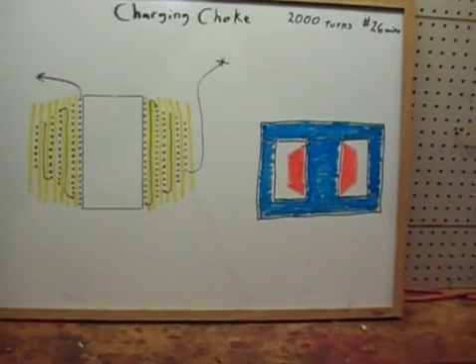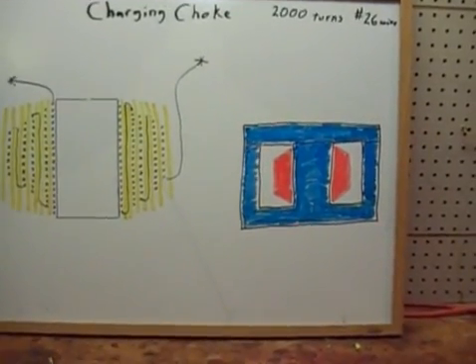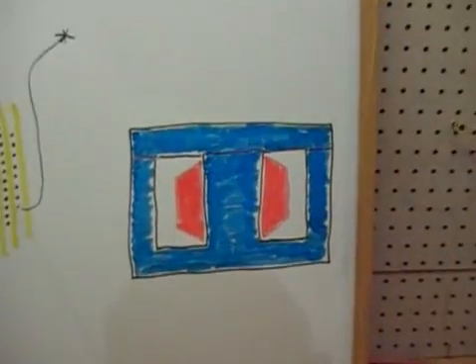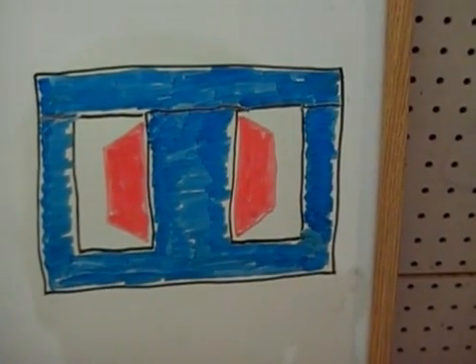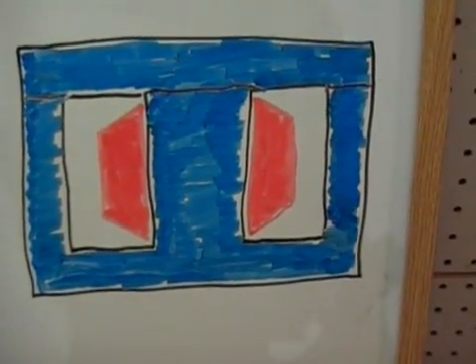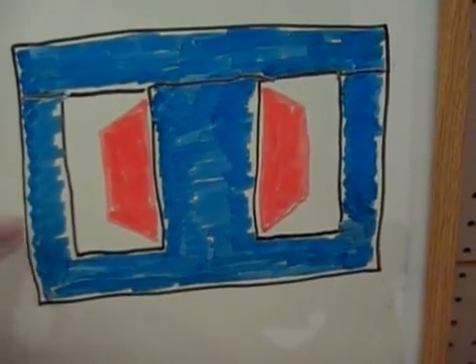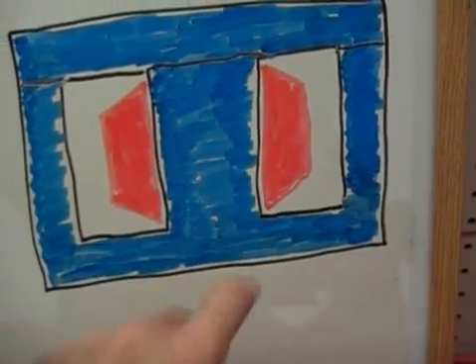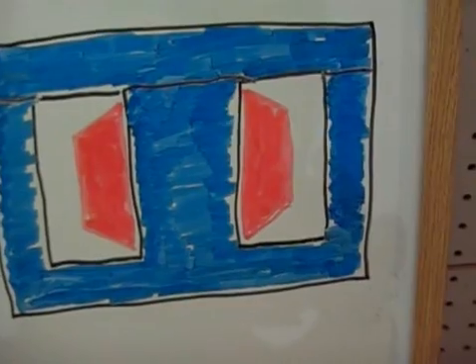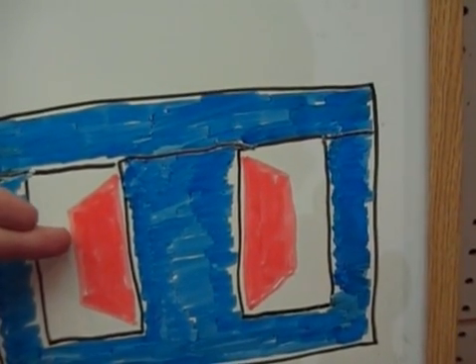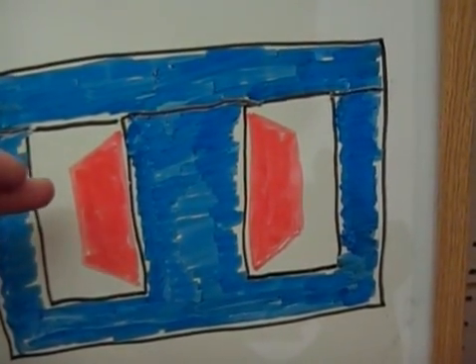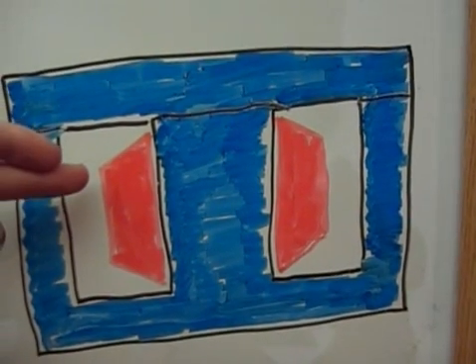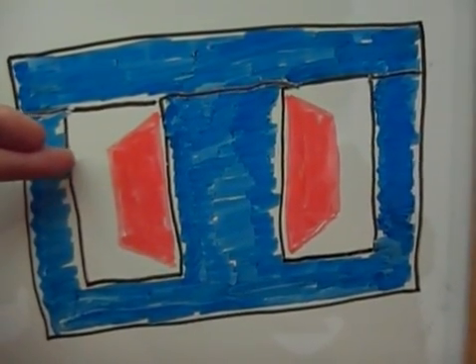You wouldn't think a coil wire would have that problem but it does. Here's a cross sectional drawing of the choke itself. The blue represents the core laminations and the red represents the cross sectional view of the winding. There's going to be a high potential between the outer part of the winding and the inner part of the winding. So you'll have a tendency for the voltage to arc over to the core if it gets too close to it.